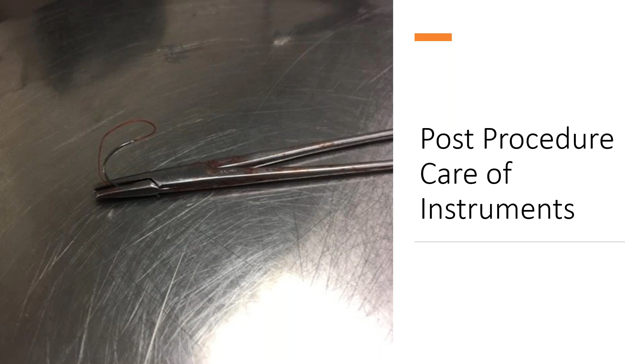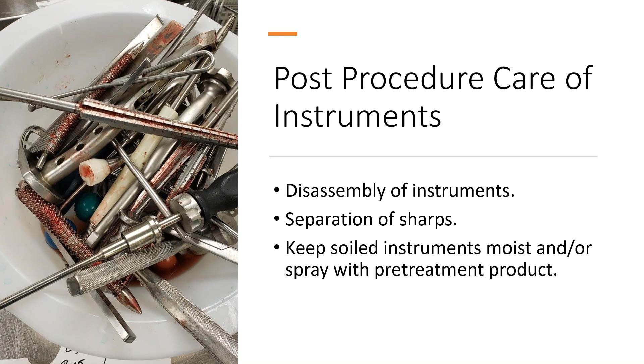But I do want to point out, even in this picture, you can see this instrument right here. This is actually a modular instrument. This should disconnect right here. And this instrument as well. This part right here should not be in there. That goes down into a cannula inside that instrument, and it should not be engaged at this point. And obviously, there's plenty of gross amounts of soil on those instruments. So there's a lot of room for improvement right there in that photograph. This post-procedure care of instruments that we're going to talk about again is supported by AORN, AAMI, AST, and manufacturers' IFUs.